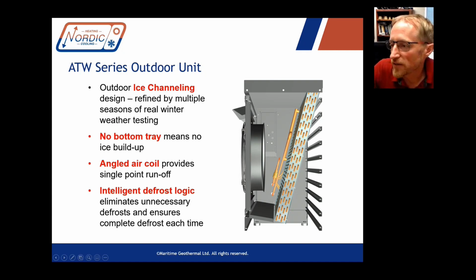We eventually came up with the design where the air coil is on a 15-degree angle. So any moisture running down the outside of the coil during defrost just runs down to a single point. I'm not sure if you can see my mouse pointer, but if it runs off to a single point, it can't really be retained there by the surface tension of the fins, and it'll drip straight off. So there's nothing there to refreeze, and there's also no bottom tray. One thing to be aware of when installing these is you shouldn't install it on somebody's front walk, because there will always be moisture coming off the coil in the winter. But as a result, we haven't had any air coil degradation issues over the 7 or 8 years that these have been in operation. So it's been very successful that way.